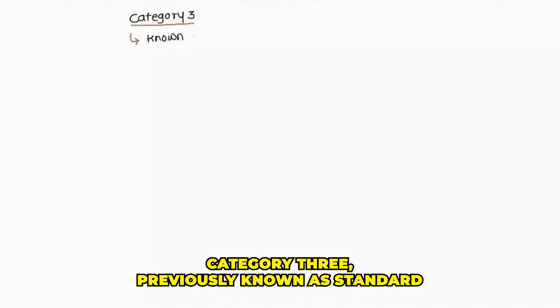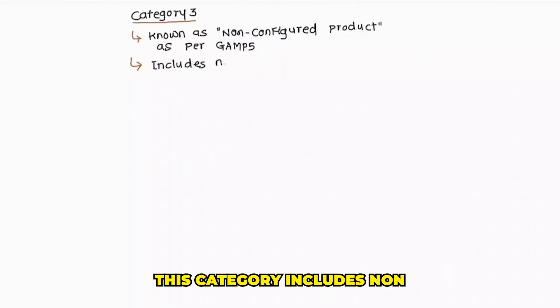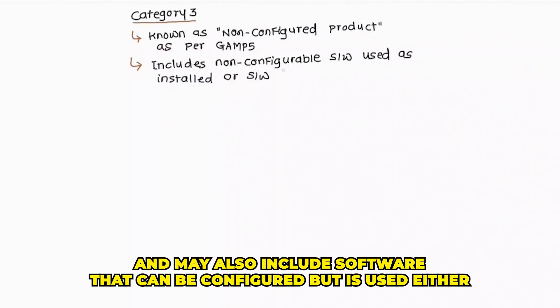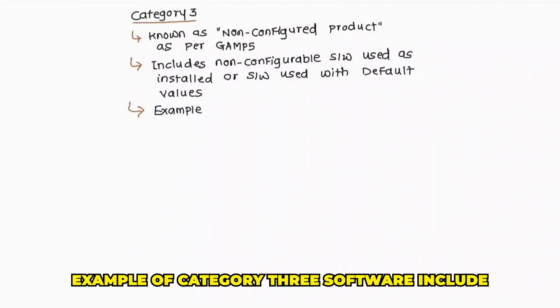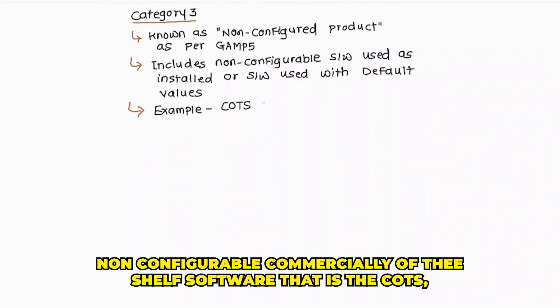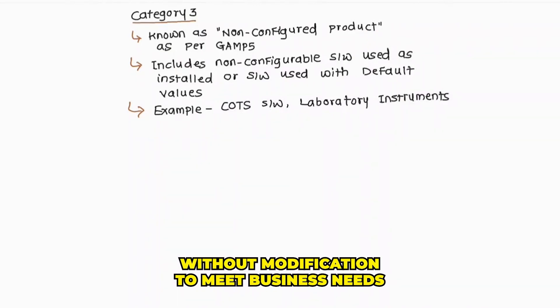Next is category 3. Category 3, previously known as standard software in GAMP 4, has been renamed to non-configured product. This category includes non-configurable software used as installed, and may also include software that can be configured but is used either unconfigured or with the standard defaults provided by the software supplier. Examples of category 3 software include non-configurable commercially off-the-shelf software (COTS), laboratory instruments, and software used without modification to meet business needs.